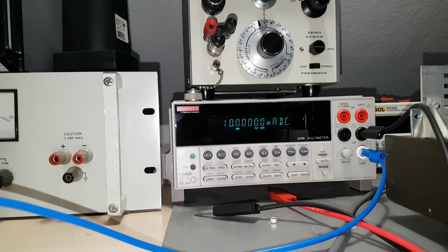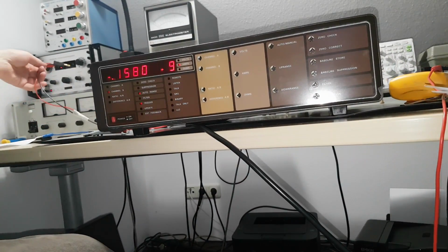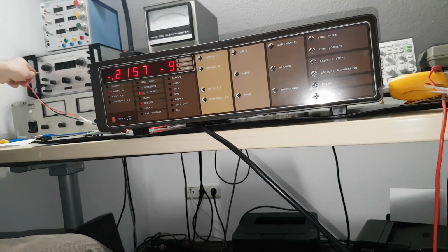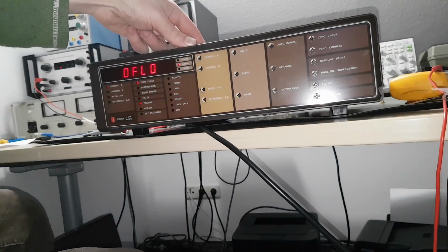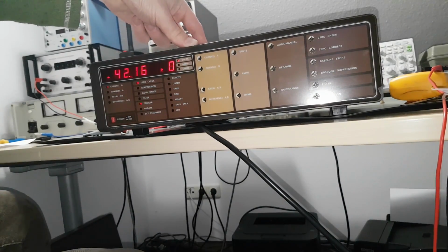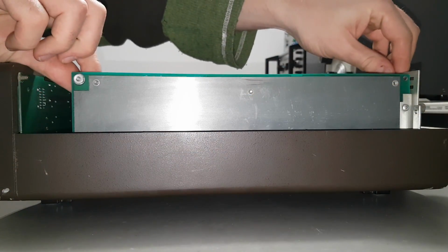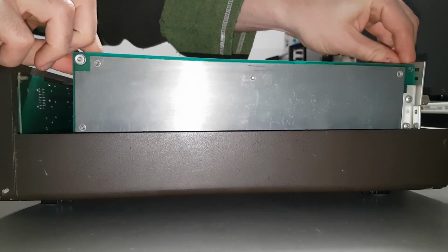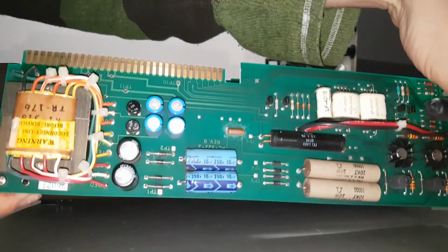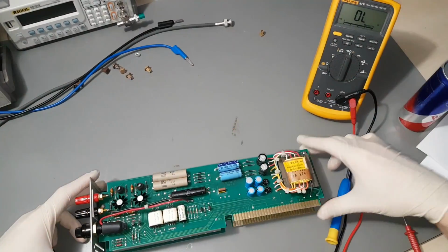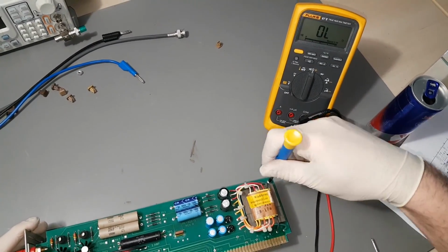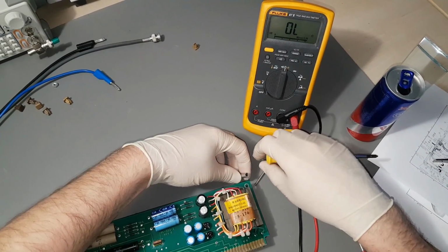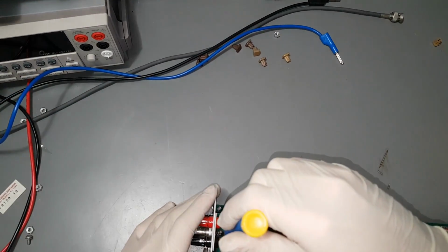10 milliamps, today's special. Channel B seems to be fine right away. Channel A, not at all, luckily. Because that gives us an opportunity to take a closer look at one of those electrometer modules. Would be funny if it turned out to be a shorted protection diode like last time. I'm wearing rubber gloves for this because some of the components on this module have a higher resistance than a human fingerprint has.